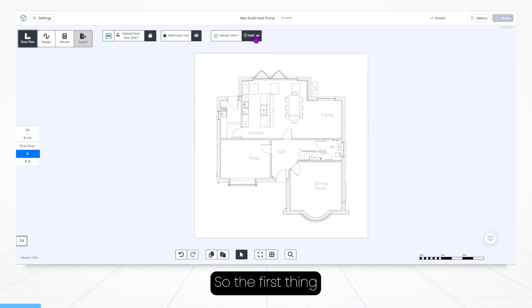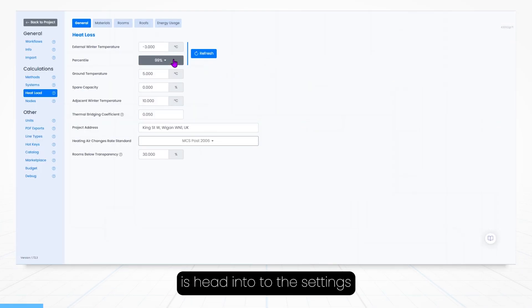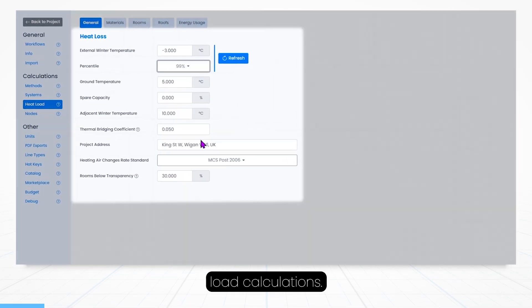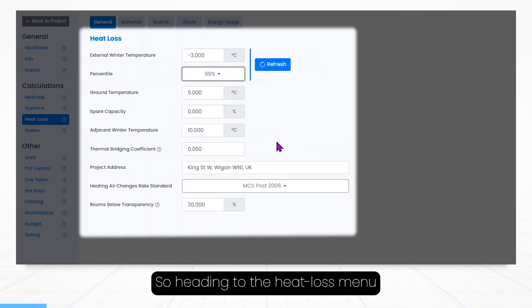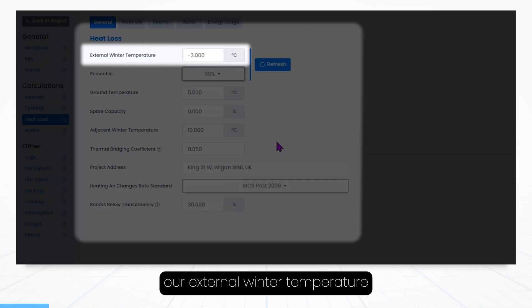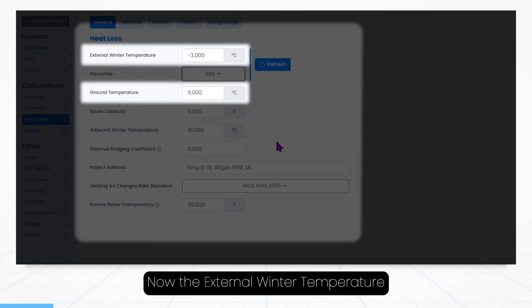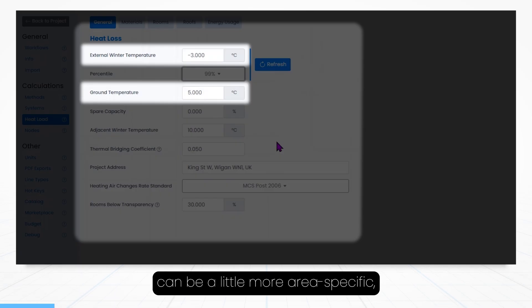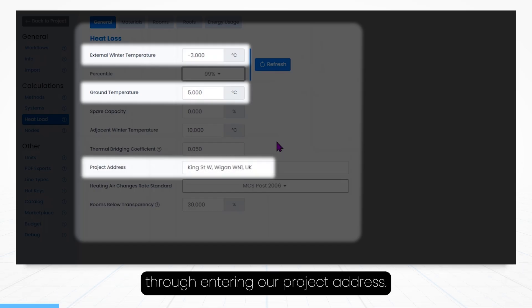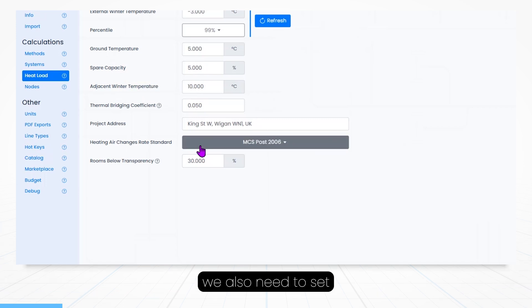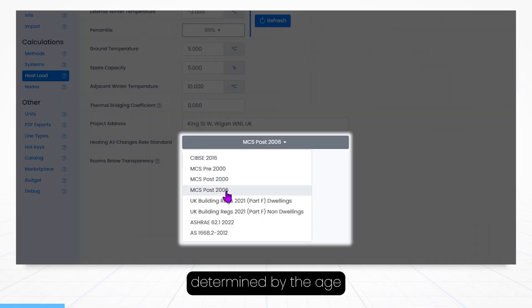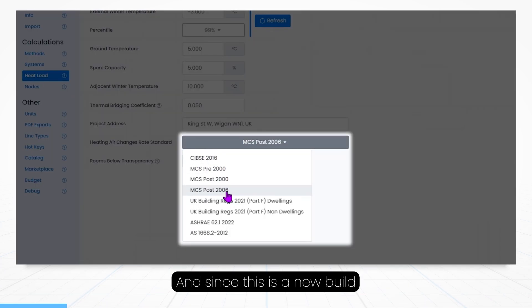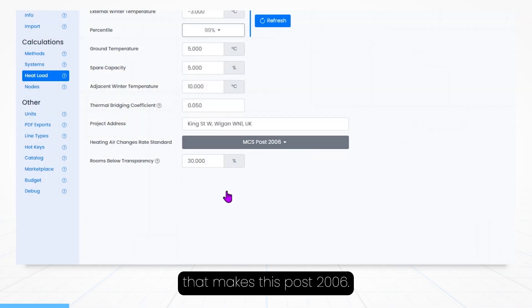So the first thing we're going to do is head into the settings and set up our heat load calculations. Heading to the heat loss menu we first set our external winter temperature and ground temperature. The external winter temperature can be a little more area specific and we can find that automatically through entering our project address. And with that done we also need to set our air change rate, determined by the age of the building and since this is a new build, that makes this post 2006.